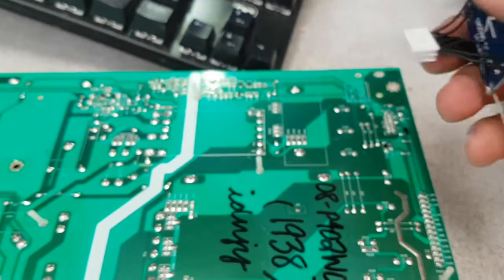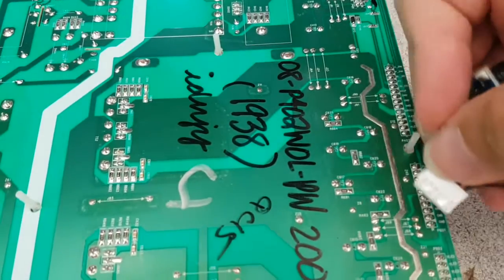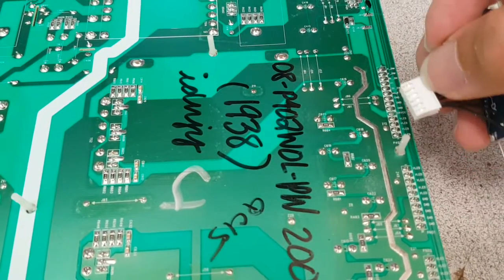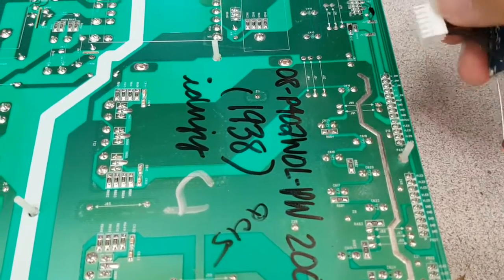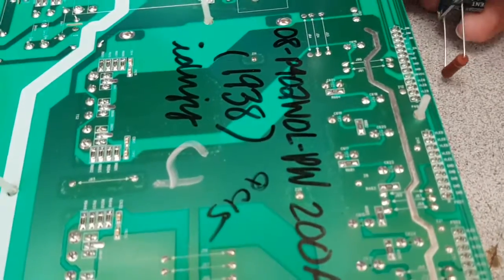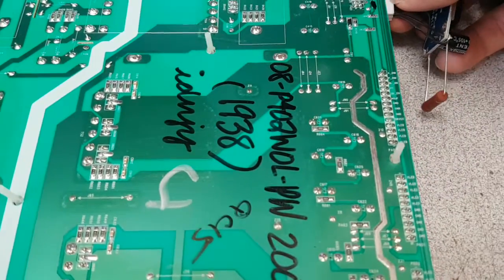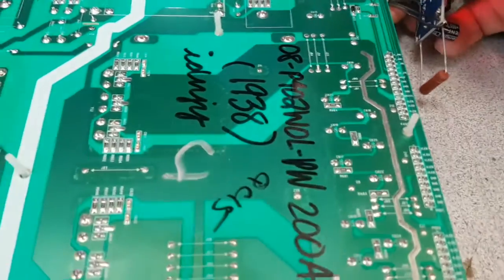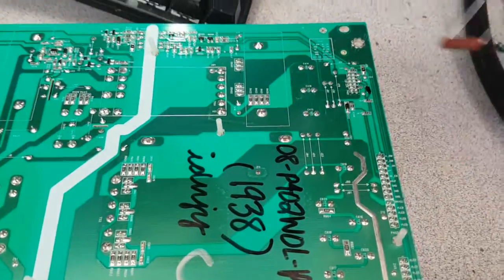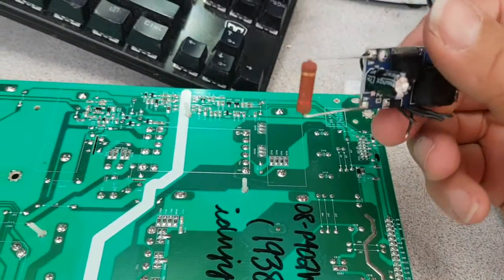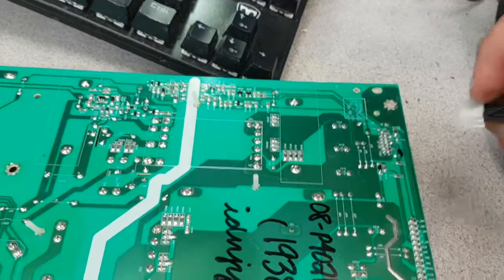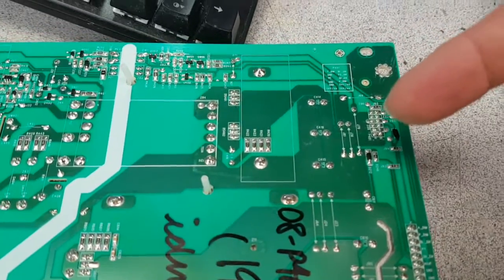I also found that if you do that, you'll start getting fluctuating, turning on and off voltage here that varies between 8 and 9 volts. I'm not going to show you that, but instead tell you something different: it will continue fluctuating until you put a load on the standby 24 volts here.